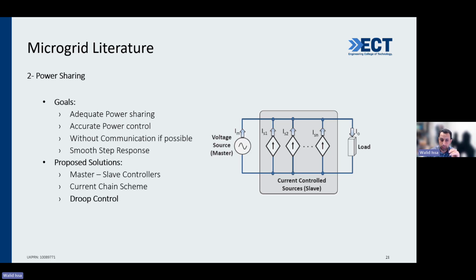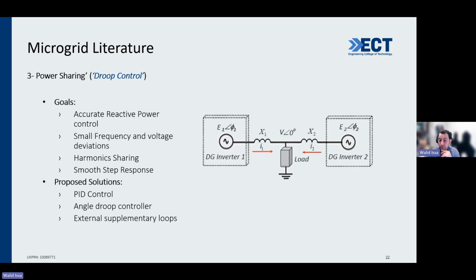You don't need to communicate at all. Now, power sharing, again, the droop control: how does droop control work, and what is the advantage of droop control? It can generate accurate power control, but unfortunately, it can generate active power control, but not reactive power control. So one of the goals is how to change that droop control to make it accurate in reactive power as well. Reactive power can be anything, so that's the problem.